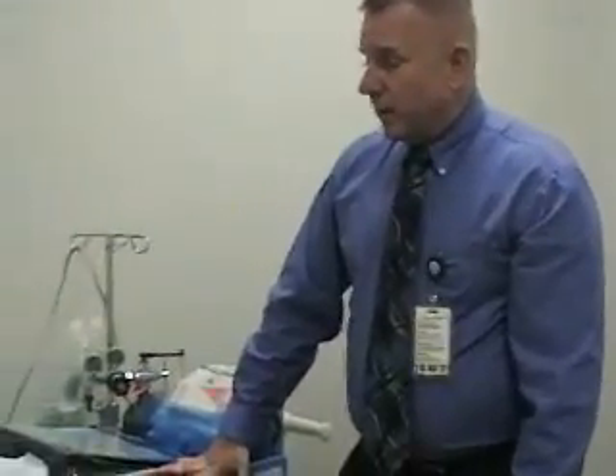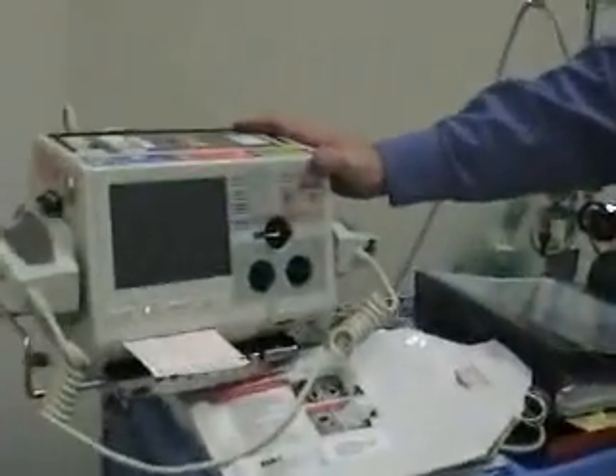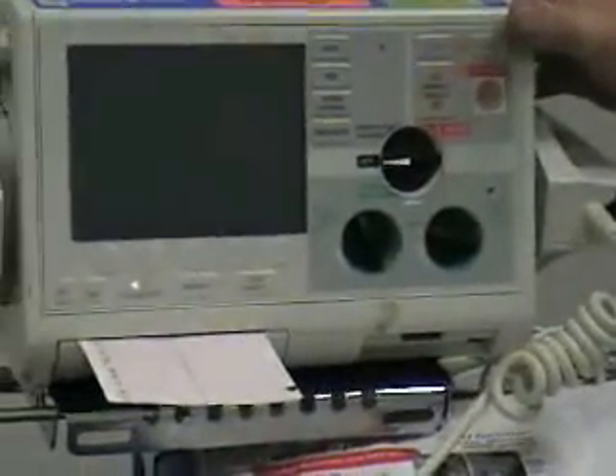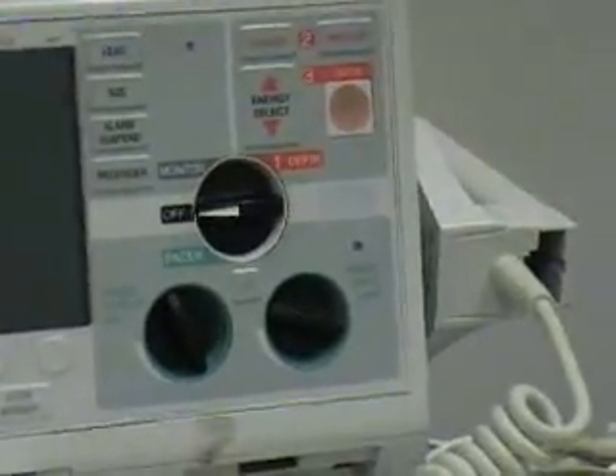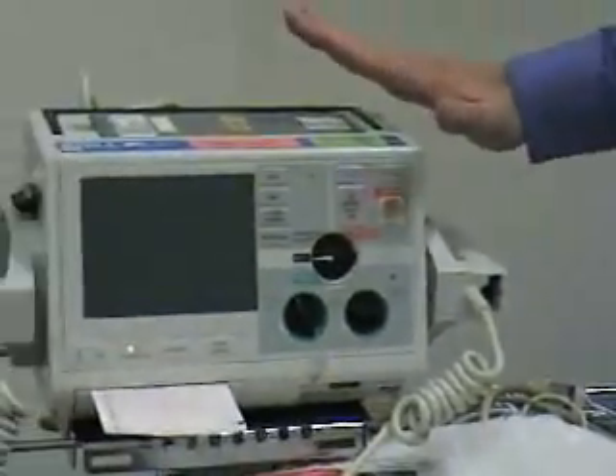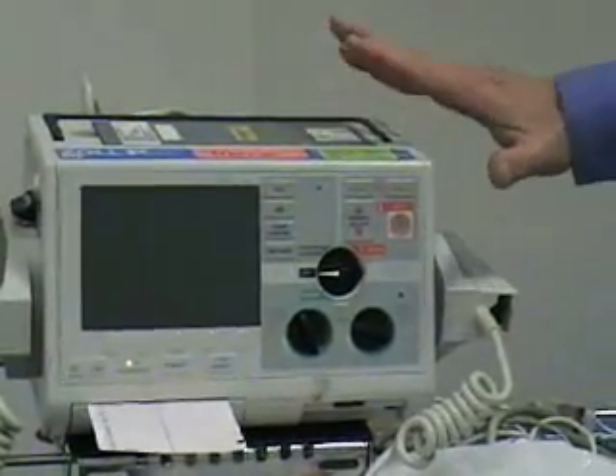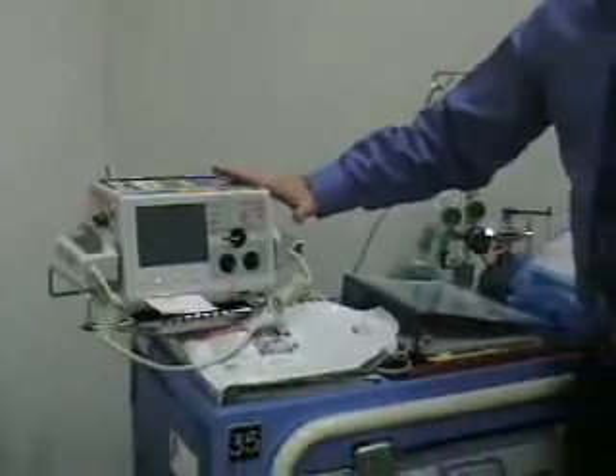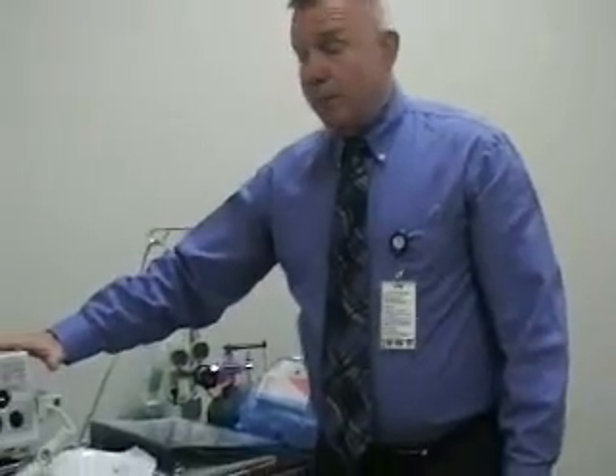The next thing that you're going to be looking at is the defibrillator itself. You'll be testing the integrity, the functioning of the defibrillator. As I mentioned before, you want to make sure that you have power. The next thing that you'll be doing is simply 1, 2, 3, and that is following the instructions. Most defibrillators these days have very simple, explicit instructions on the front of the defibrillator that tells you exactly what you need to do, and it's almost as if you were doing an actual defibrillation itself. The big difference here is that you'll be putting it into a test mode, and you'll only be using a minimal amount of energy in order to save the integrity of the inner workings of the defibrillator. So, remember, with CPR, remember your ABCs and your 1, 2, 3s, just like you learned in kindergarten, okay?